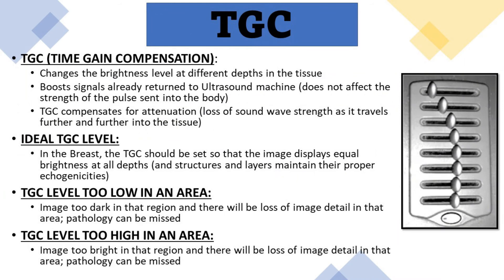The next brightness control is called TGC, or time gain compensation. TGC changes the brightness level at different depths in the tissue, and each of the TGC knobs can be adjusted separately to adjust the brightness at that specific depth. TGC boosts signals already returned to the ultrasound machine, so it does not affect the strength of the pulse sent into the body. TGC compensates for attenuation, which is the loss of sound wave strength as it travels further into the tissue. In the breast, TGC should be set so that the image displays equal brightness at all depths and structures maintain their proper echogenicities.